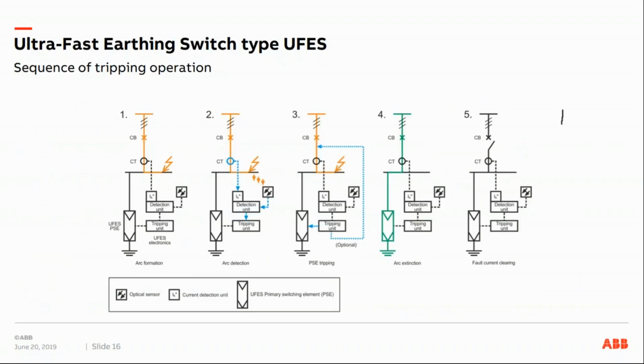The tripping of the ultra-fast earthing switch first of all requires a rapid and reliable detection of an arc fault in a defined protection zone of the switchgear system. So here you see one feeder solution where you have, let me get the spotlight again, the UFES, a tripping unit, and the detection unit for current and light sensing. Here you have the circuit breaker. Assuming that you have a fault here, let's have a look at what's happening. The specific fault is detected either by an external arc fault detection system, which is combined with a UFES electronic tripping unit, type QRU100, for instance, or alternatively by an expandable UFES electronic detection and tripping unit, type QRU1.